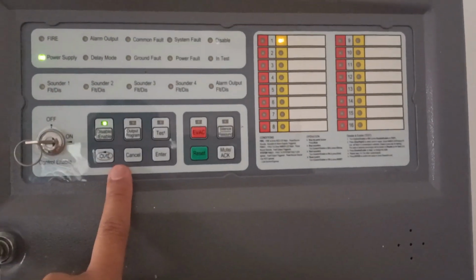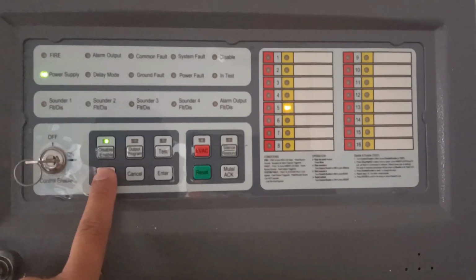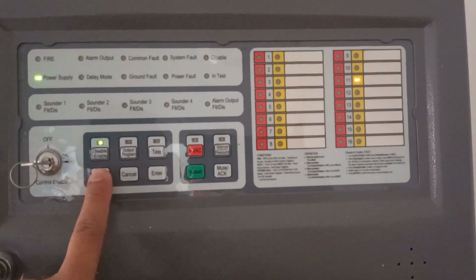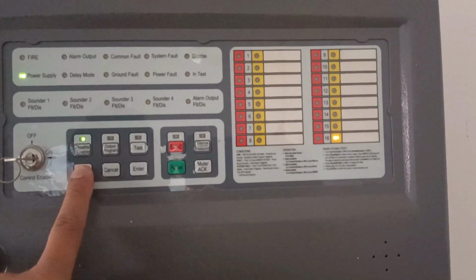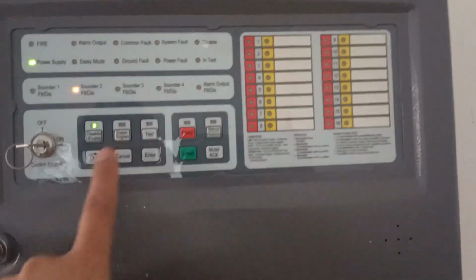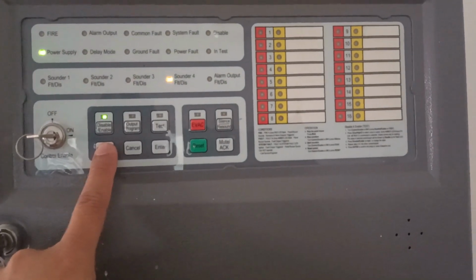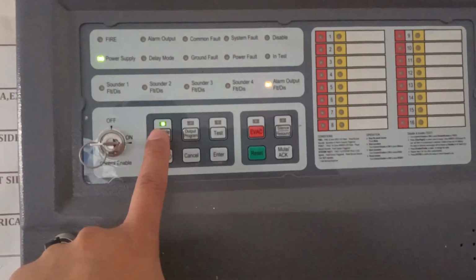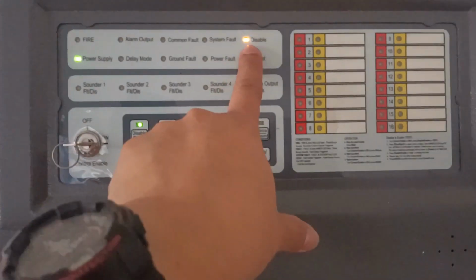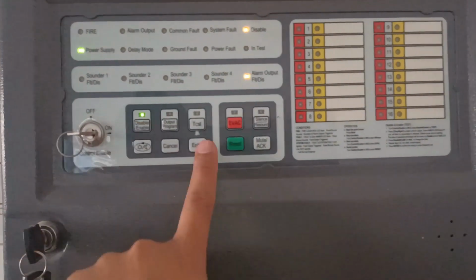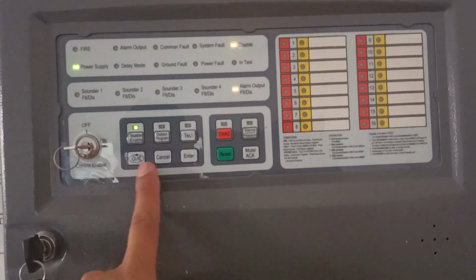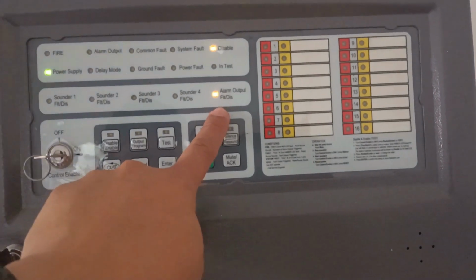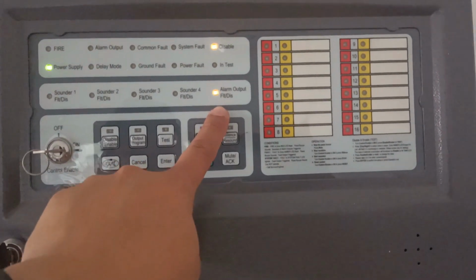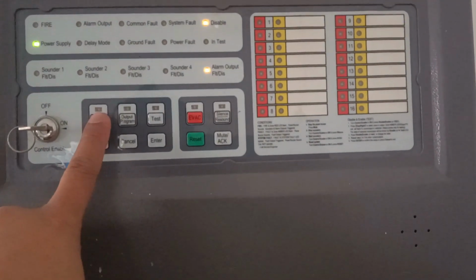If you want to disable all outputs, so no alarms from any output, it is the same procedure. You go to disable and then scroll down until you come to the alarm output. Press disable, so you make it disabled, then enter, then press cancel. Now the alarm output is all disabled.